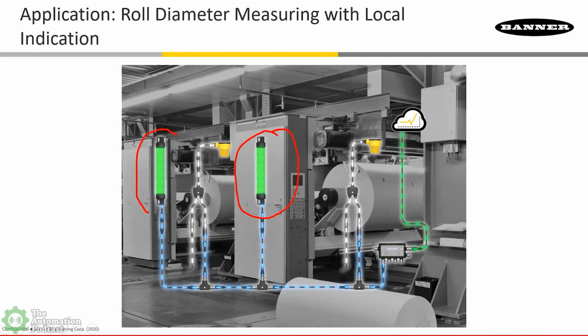So on that same branch, if you had analog sensors mounted above some rolls monitoring your raw material, and you wanted to bring that 0 to 10 volt or 4 to 20 milliamp data and set up dashboards in the cloud, you could certainly do that. You could have multiple analog sensor signals converted to a unified protocol with those converters, and set up very simple dashboards.